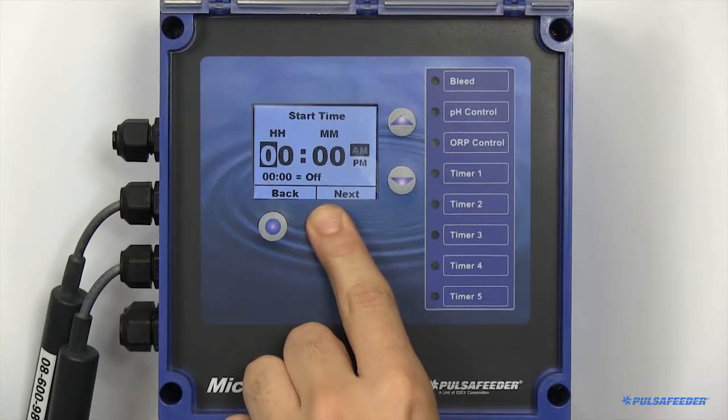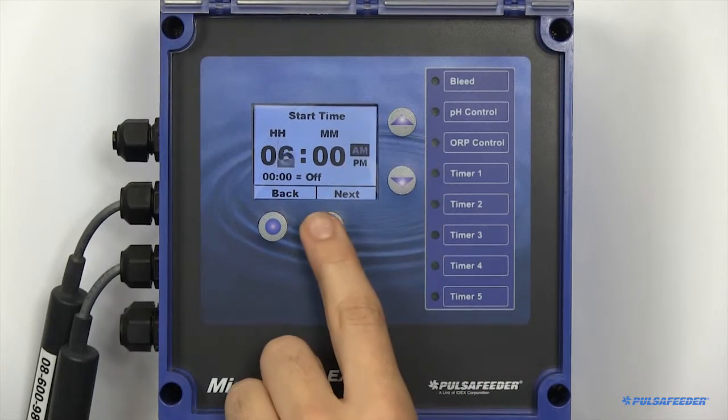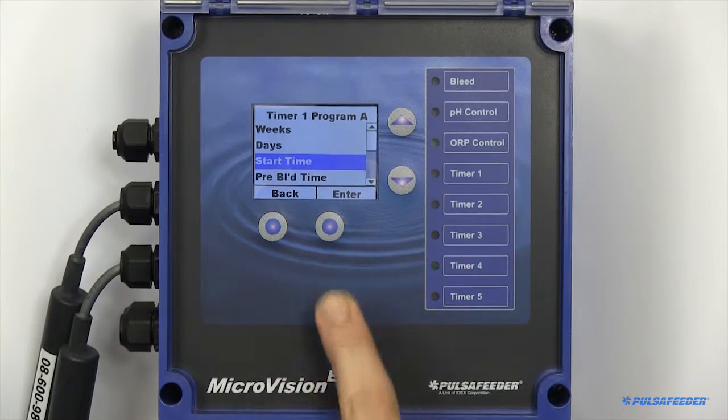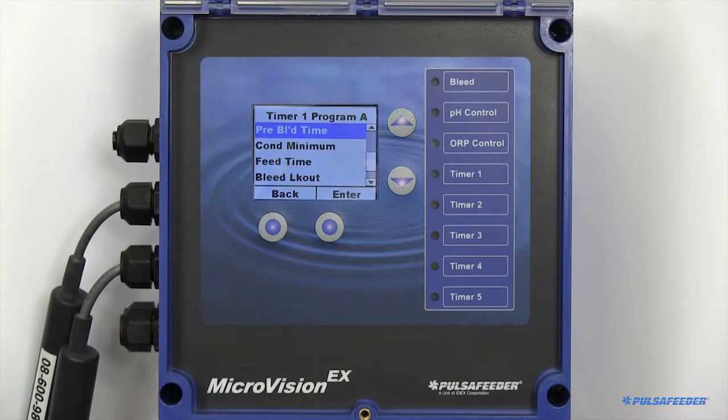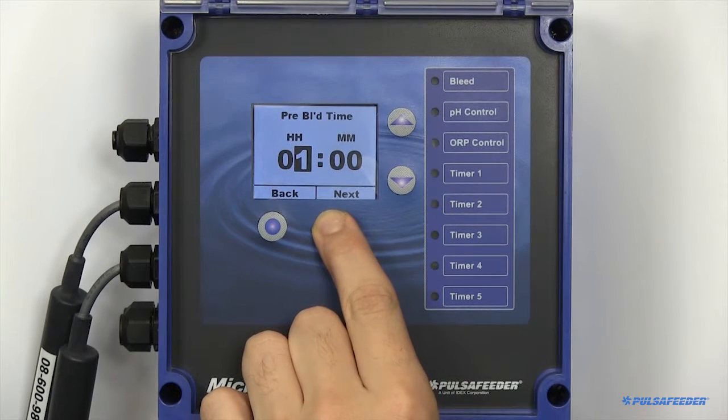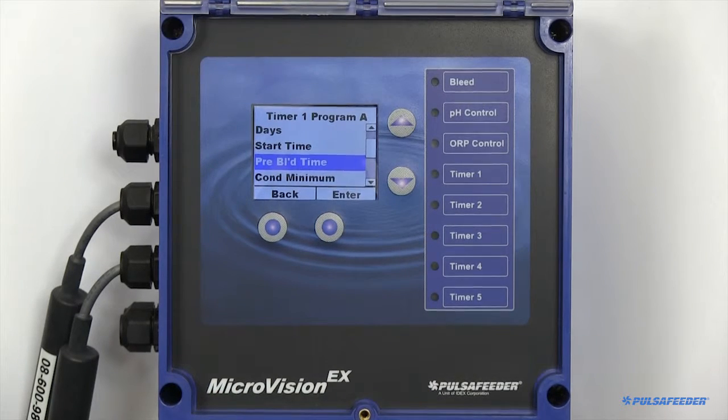The start time is when you would like to either begin your feed cycle or a prebleed, if applicable. A prebleed time is the maximum amount of time you would like the bleed function to be force enabled prior to a feed cycle.